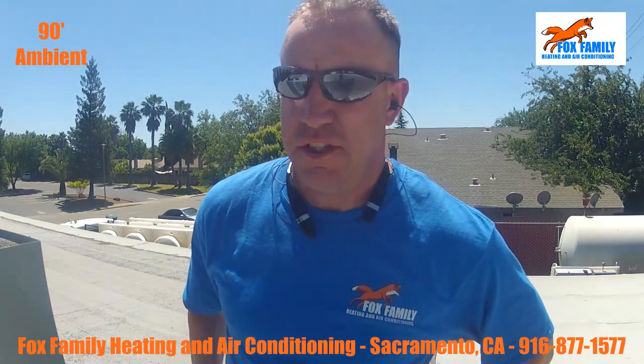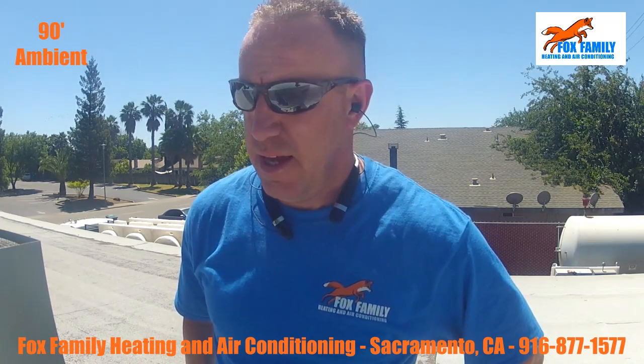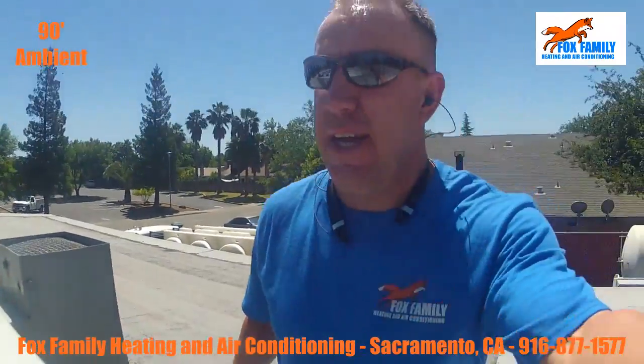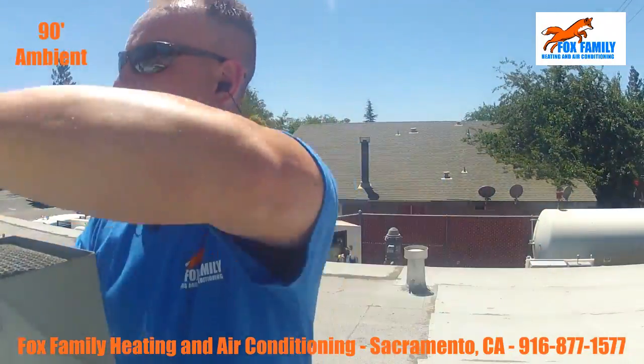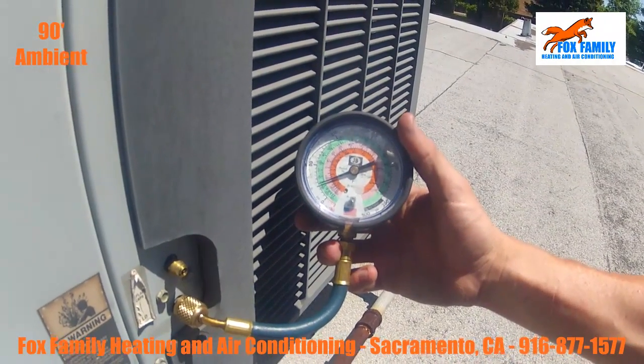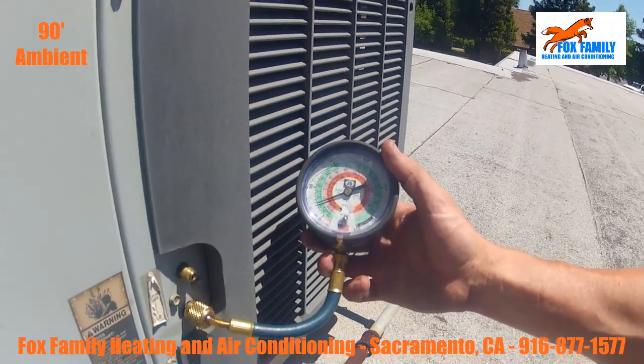Okay, a call here was that she said she had a power outage a couple days ago, and now the AC won't work. So I get up here, I turn the AC on, and my fan is blowing. So let's see what else is going on here. Initial reading, less than 25 psi, R22 system, so that's not good.